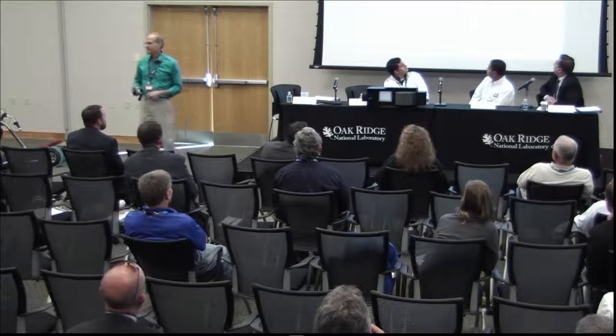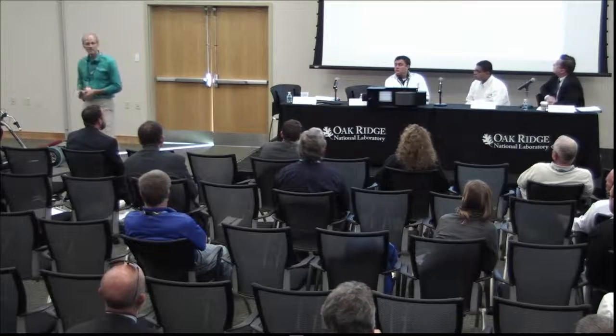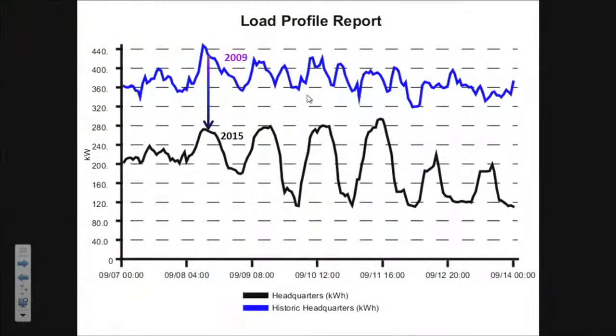So why do this? I do the commercial industrial energy efficiency for our electric utility. We have very good performance. We've got a 40% reduction. This was changing the CO2 setting from 50% down to about 30%.